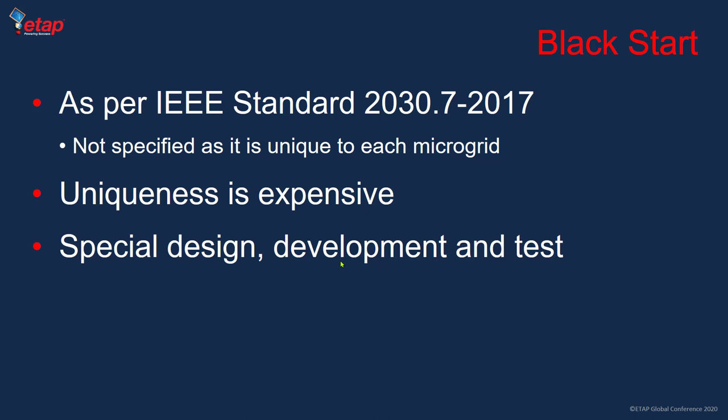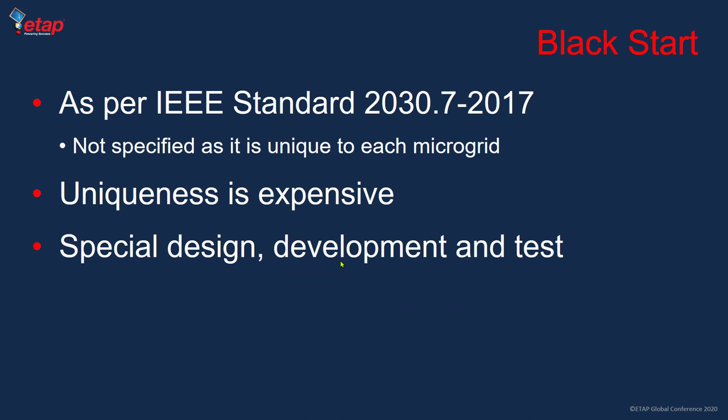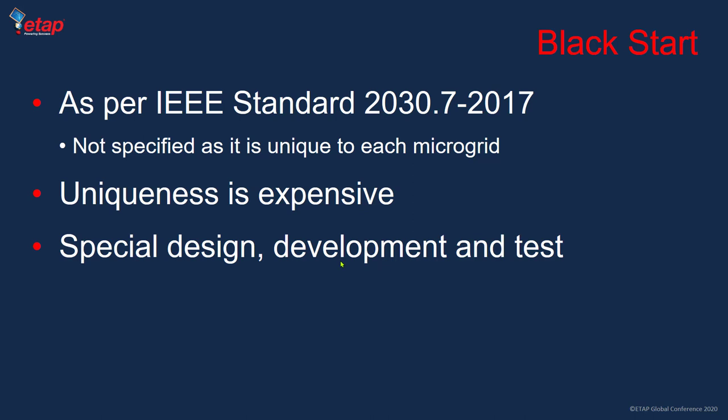Black start is unique to each microgrid and can be expensive in terms of special design, development, and testing. However, if we do a very good job on unplanned islanding — using intelligent dynamic strategies as ETAP provides — we can avoid the black start and eliminate this expensive unique design requirement.